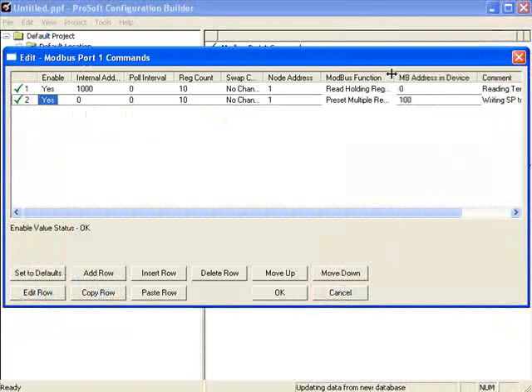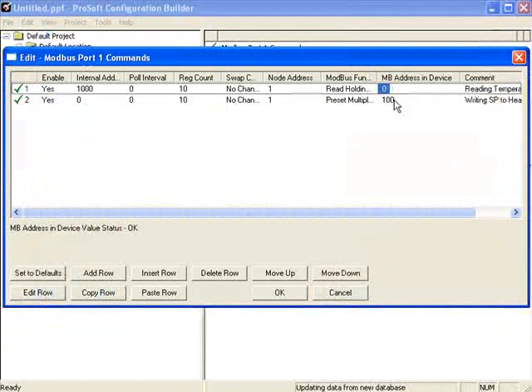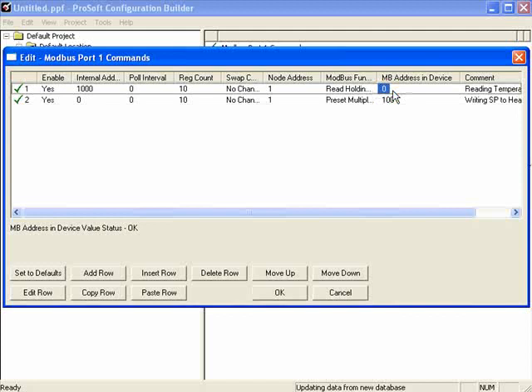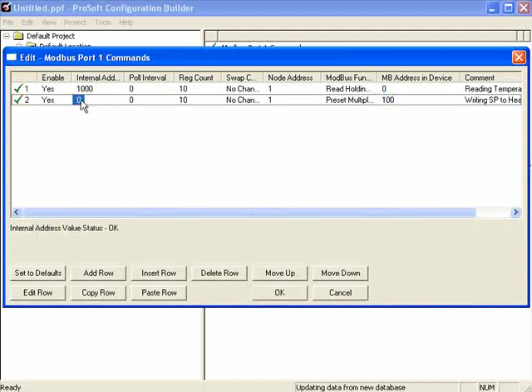Expanding the view, we see that the first command reads values from address 0 in Modbus address in device — in other words, reading from 40001, the very first holding register — and places them in address 1,000 of the internal database on the MVI69 MCM. The second command writes 10 registers to address 40101 on the Modbus device, node number one, getting those values from address 0 of the internal database. Click OK — that's good for node one.